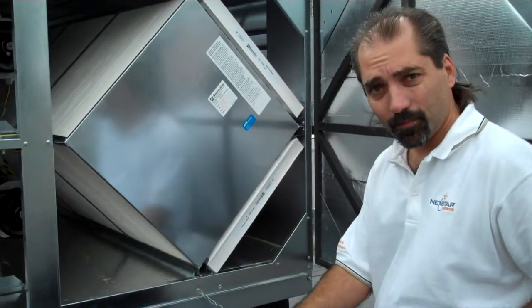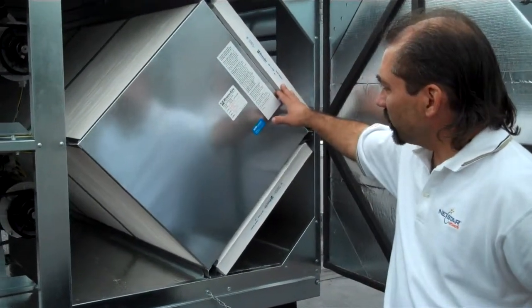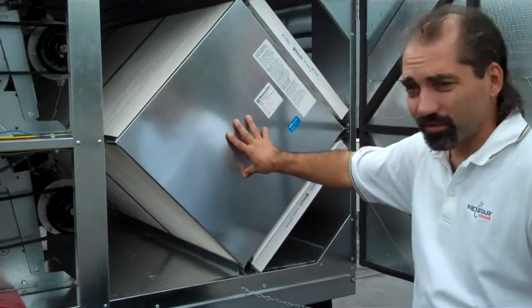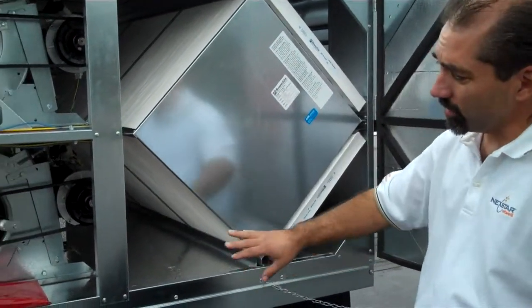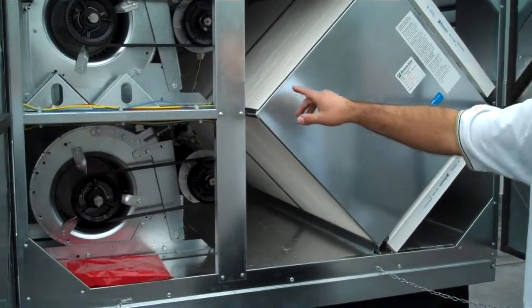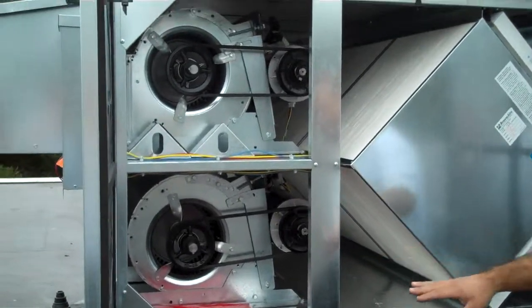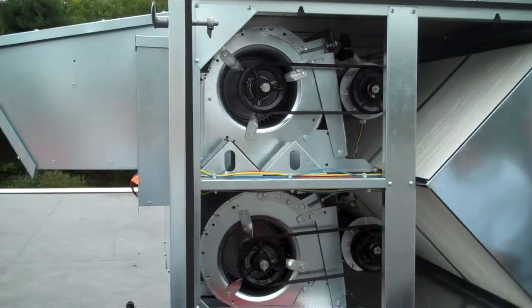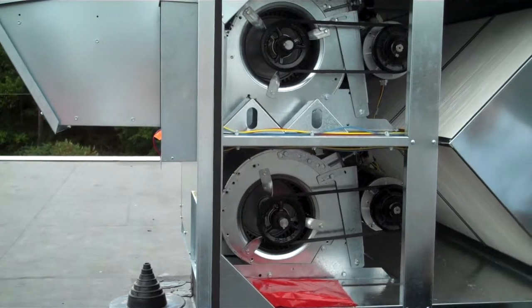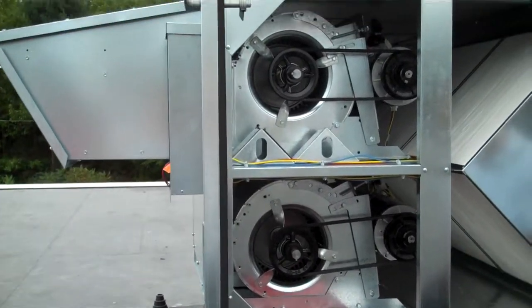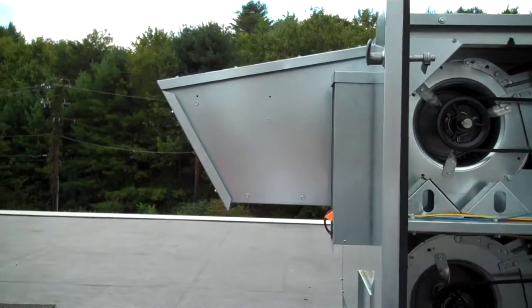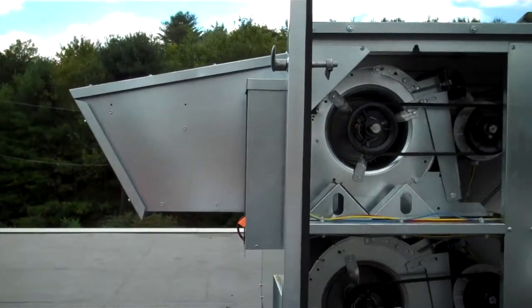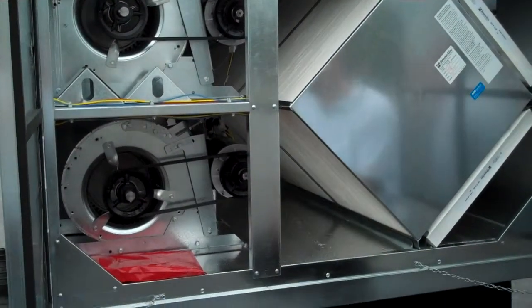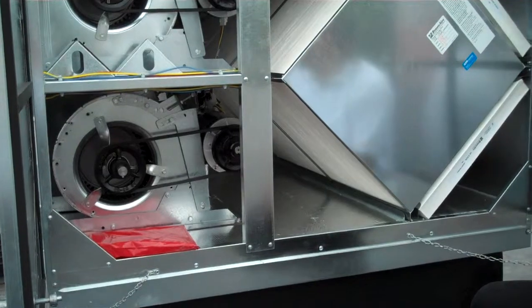So this will need some maintenance. Absolutely. These filters will need changed every 3 months, the core once a year. And basically what you have is 2 blower motors, one for supply air, one for return air, and once we get the system up and running, we'll have to do an air balance to make sure that the system's working properly. So one's connected to a fresh air damper that's sticking outside on the roof, and the other unit is connected to the ductwork that we saw.